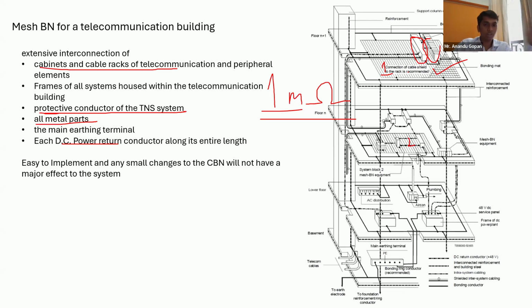So at the end of the day, even after you design such a system, how you install it matters a lot. If your installer is not proper, such a system will never work out. So mesh sizing depends on this 1 milliohm requirement and the 6 microhenry requirement. And you can see that this conductor is your reinforcement. You are connecting your reinforcement to these places, or you can lay it along with your reinforcement. Basically, no change, but you should have some tap-off points to connect to those points.